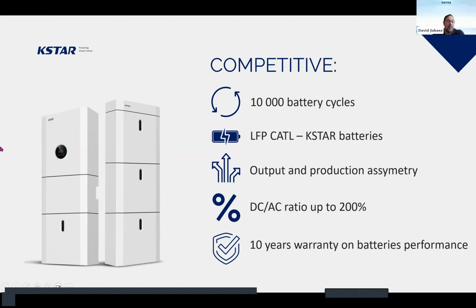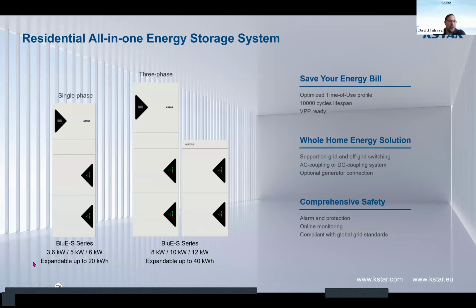The DC to AC ratio can go up to 200%, and this is the new design of the system. Regarding the topology, for the one phase it can go with 3.6 kilowatt, 5 kilowatt, and 6 kilowatt rated power of inverter, and the storage capacity can go up to 20 kilowatt hour. For the 3-phase, it can go up to 40 kilowatt hour storage capacity, with 8 kilowatt, 10 kilowatt, and 12 kilowatt rated power of hybrid inverter.